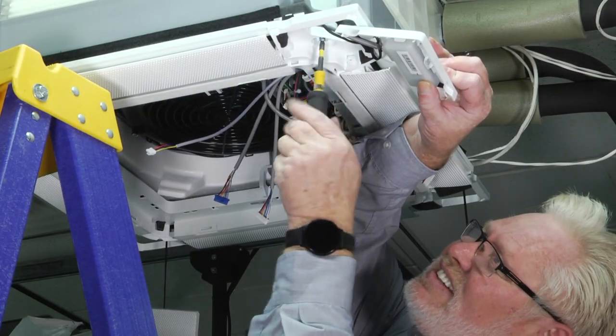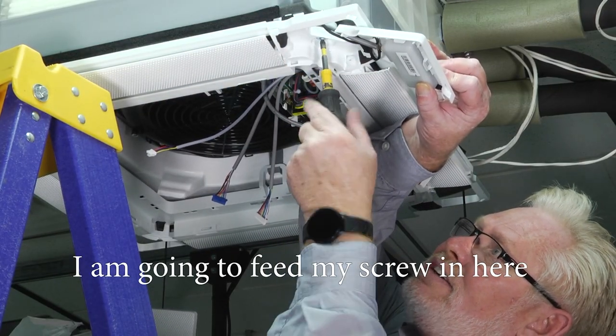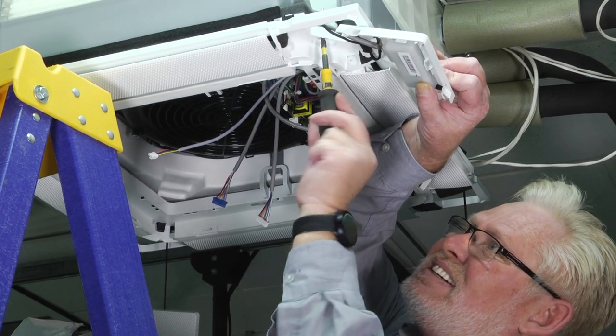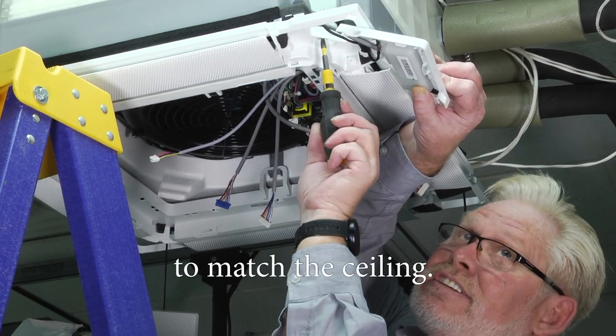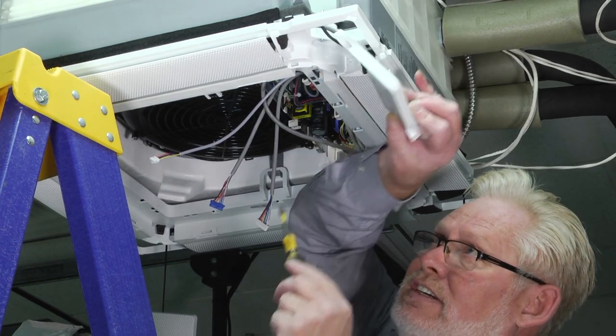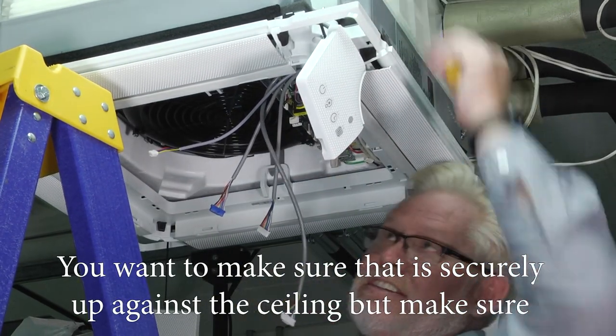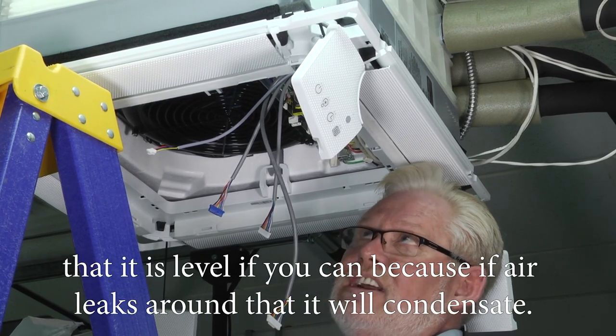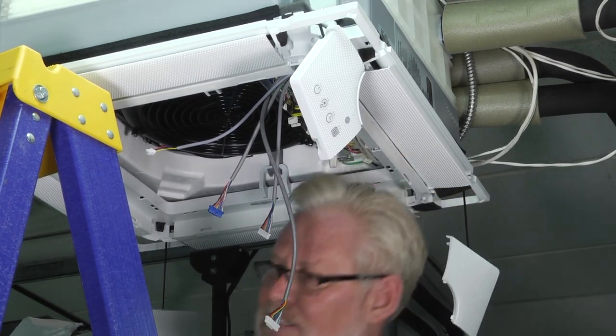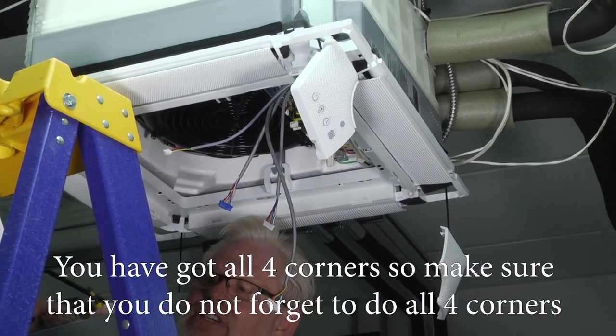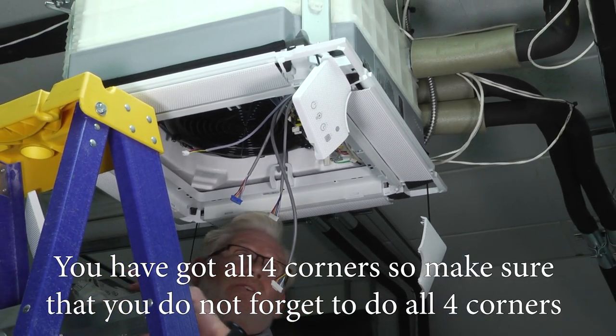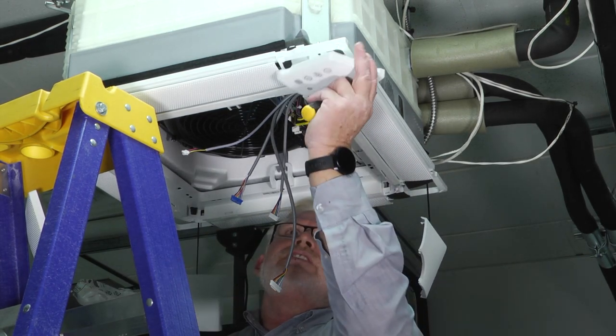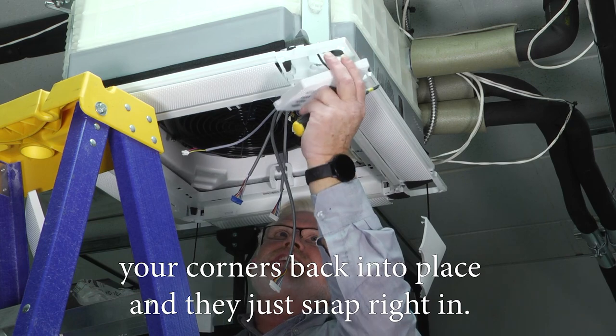I'm going to feed my screw in here and that will adjust this panel up or down to match the ceiling. You want to make sure that's securely up against the ceiling, but make sure it's level as you can, because if air leaks around that it will condensate. You got all four corners, so make sure you don't forget to do all four corners. Once you're done, you're going to reattach your corners back into place and they just snap right in.